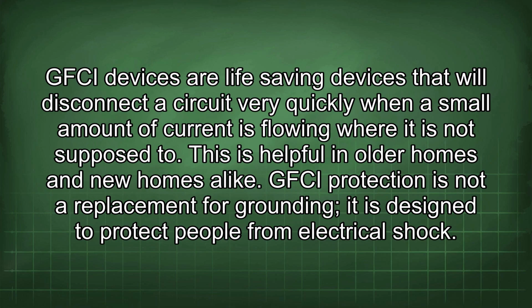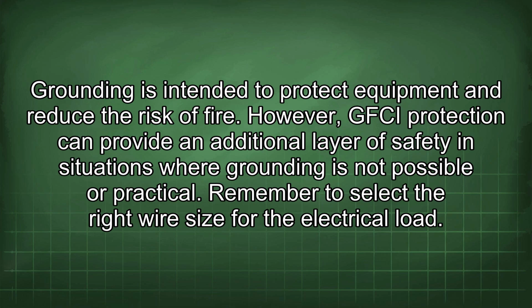GFCI devices are life-saving devices that will disconnect a circuit very quickly when a small amount of current is flowing where it is not supposed to. This is helpful in older homes and new homes alike. GFCI protection is not a replacement for grounding; it is designed to protect people from electrical shock. Grounding is intended to protect equipment and reduce the risk of fire. However, GFCI protection can provide an additional layer of safety in situations where grounding is not possible or practical.